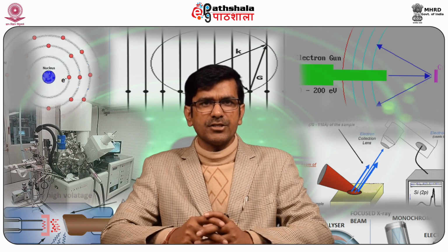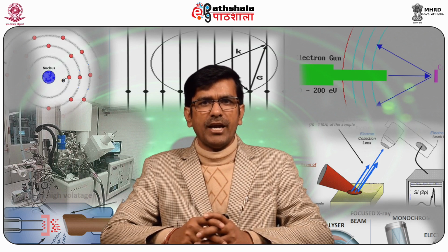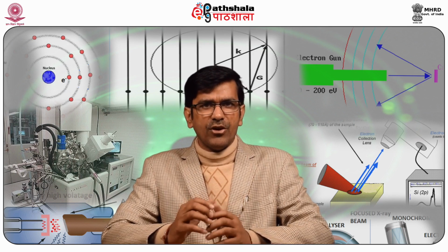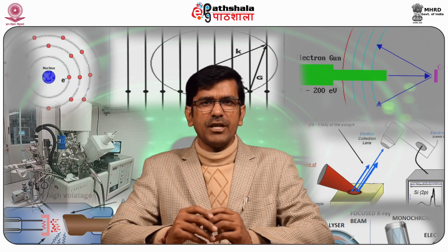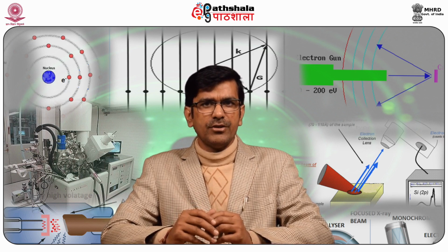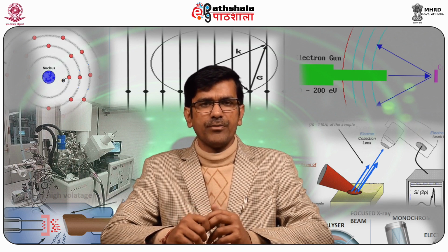Now, let us discuss vacuum. Vacuum is an important requirement for the analysis as the instrument is kept under ultra-high vacuum. The level of vacuum in SIMS is the highest among all the analytical instruments and requires utmost care along with sample preparation and the maintenance of the equipment.